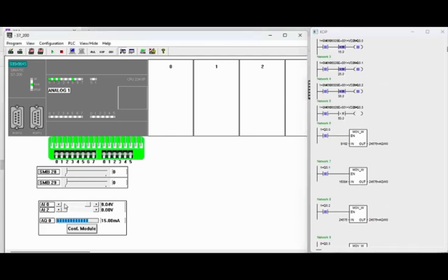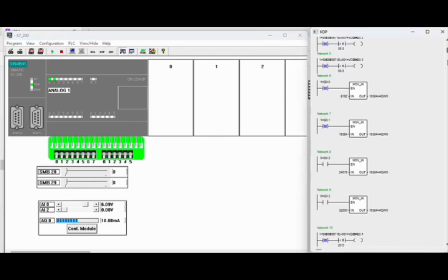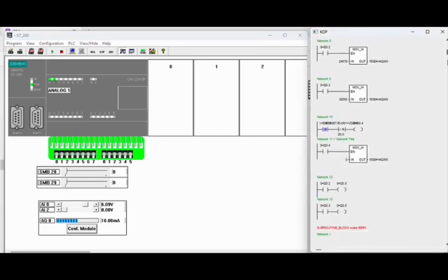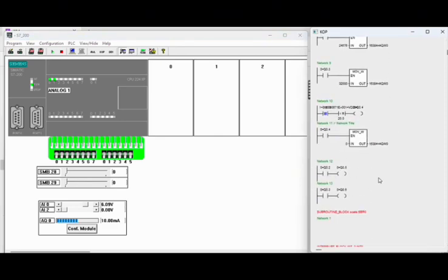As water continues to decrease, the radar sensor sends the level at 10 milliampere, which turns off the high level, and now we are back at medium level for 10 milliampere. High level indicator is turned off, and pump number 1 is turned off as well. So no more pumps running at this time since we are at the medium level.